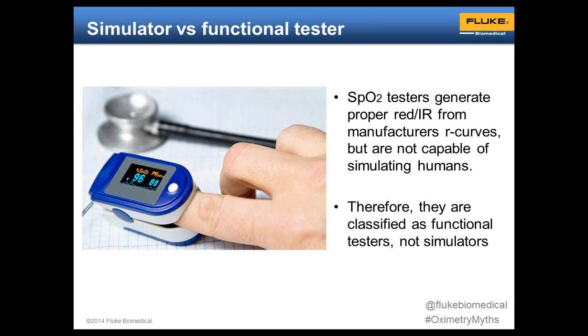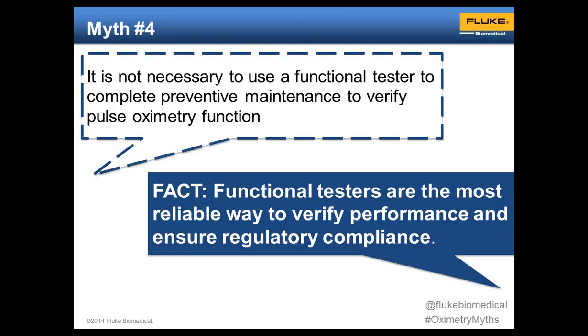Next myth. It is not necessary to use a functional tester to complete preventative maintenance to verify pulse oximetry. Fact. Functional testers are the most reliable way to verify performance and ensure regulatory compliance. As most of you saw, CMS issued some guidance a while back, I think in December, about following manufacturer guidelines or creating your own risk management program. This is where we highly encourage you to go back and look at the manufacturer's recommended maintenance in the manual, which will talk about the use of a functional tester. I think there are some people out there that still do use a finger once in a while, your own finger, to test the pulse oximeter, and that may not be the most accurate way to do that.